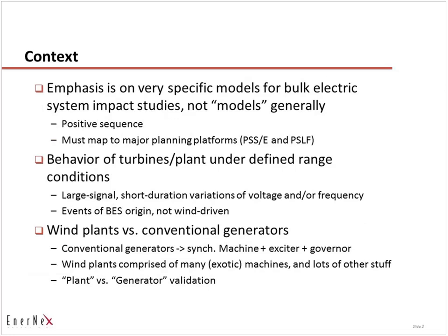The context is not models generally, but positive sequence models mapped to the major planning platforms: PSSE, PSLF, and PowerWorld, which cover the interconnections in the U.S. We're talking about the behavior of renewable plants under defined conditions: large signals, short-duration variations of voltage and/or frequency, and events of BES origin — not events internal to a particular plant or driven by wind or changes in solar irradiance.